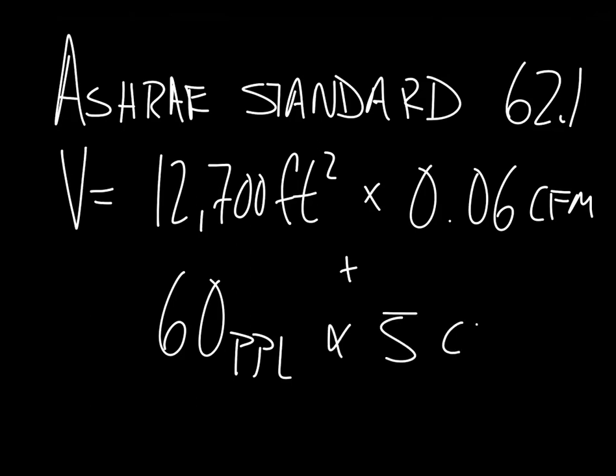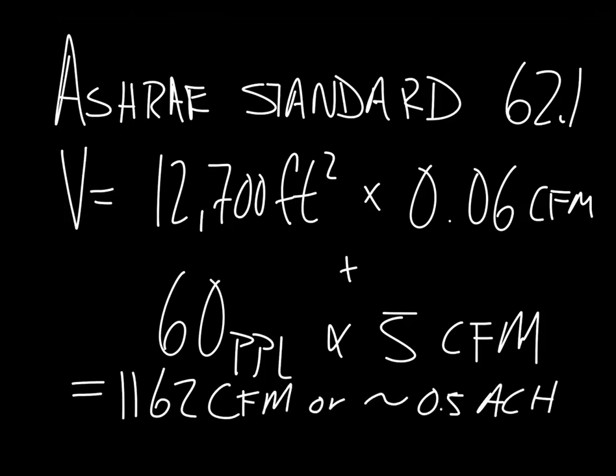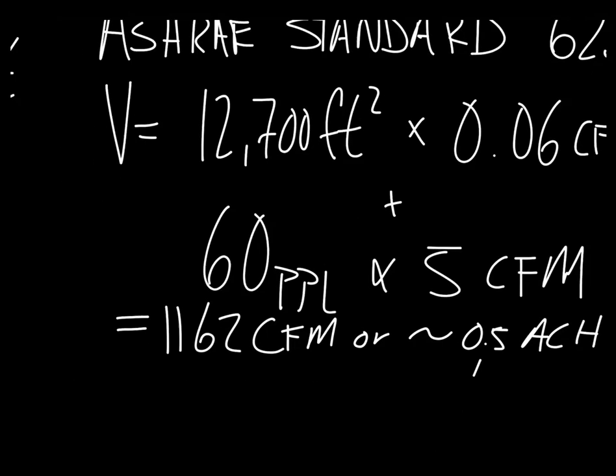we need to account for the occupants. The 60 workers require 5 CFM each. This brings us to a total of 1,062 CFM. Assuming 10-foot ceilings, this is about half an air change per hour.